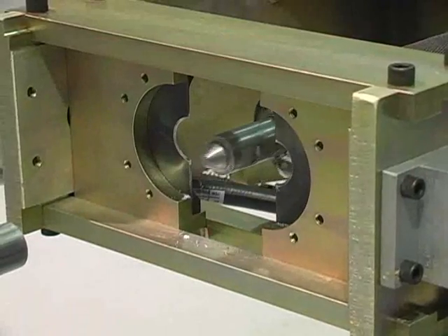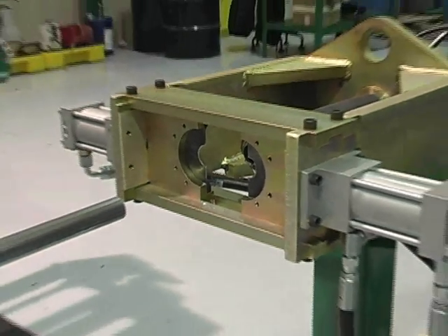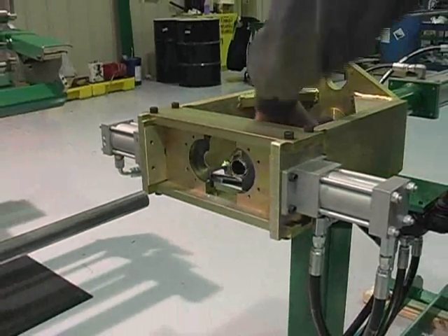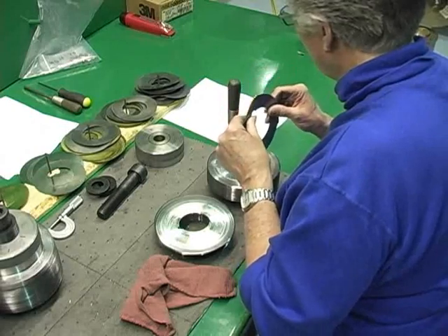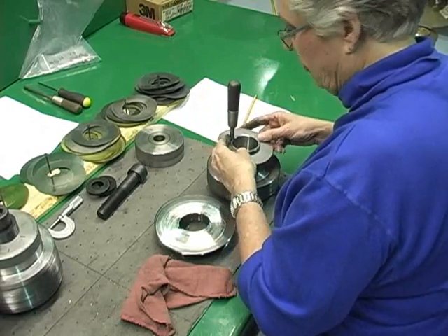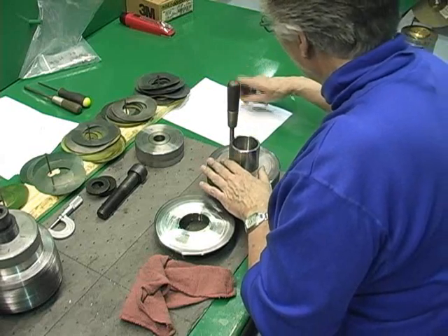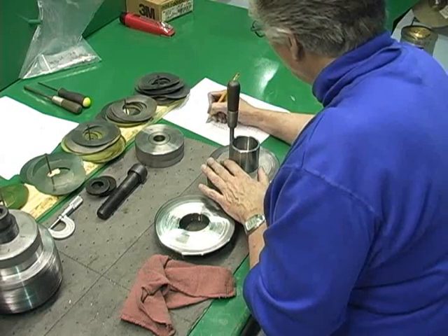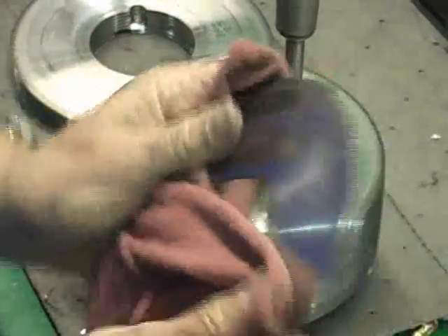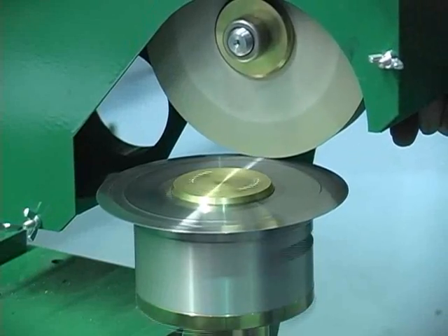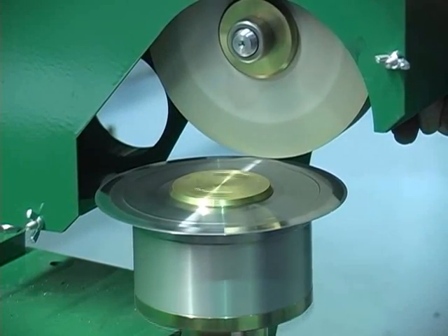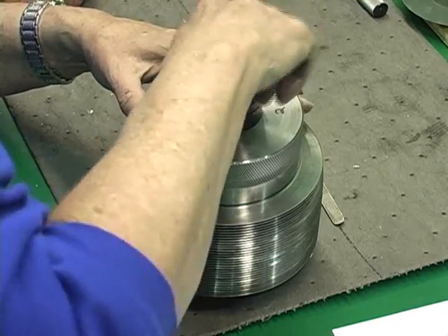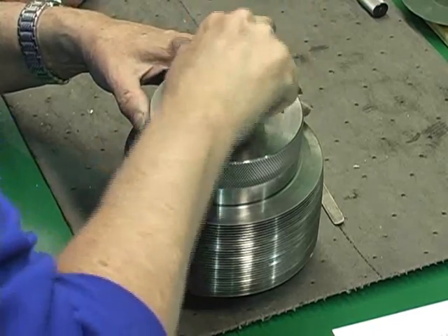The pusher mandrel can be adjusted for a specific tube OD and wall thickness and the amount of material to be stripped back from the tube. The successful operation of the Model B extruded fin tube machine depends greatly on the quality of the aluminum muff and the disc maintenance program. Disc maintenance requires meticulous attention to detail and involves the removal of the discs from the machine, cleaning them in solvent, and then wiping them thoroughly while inspecting each disc closely for cracks and or nicks. Damaged discs should be replaced. After inspecting the discs, each is then carefully polished and assembled in disc stack sequence before being placed back in the finning head of the machine.